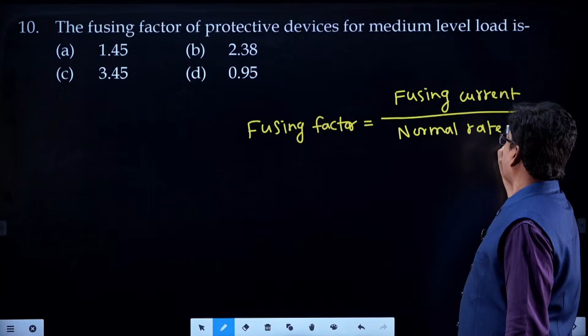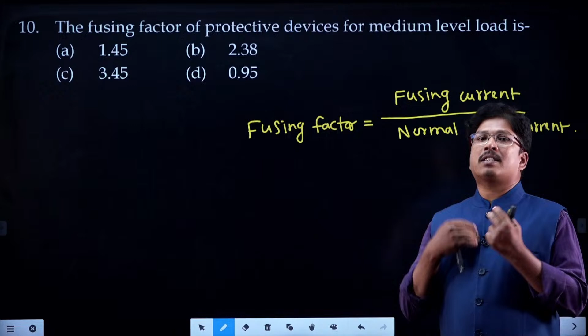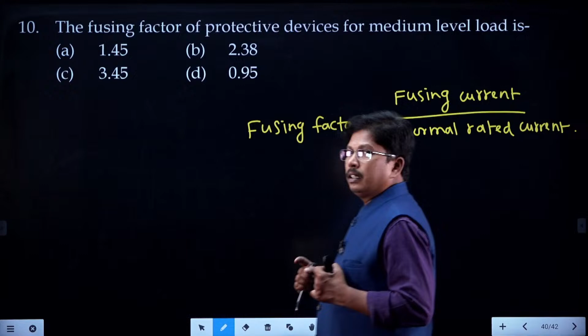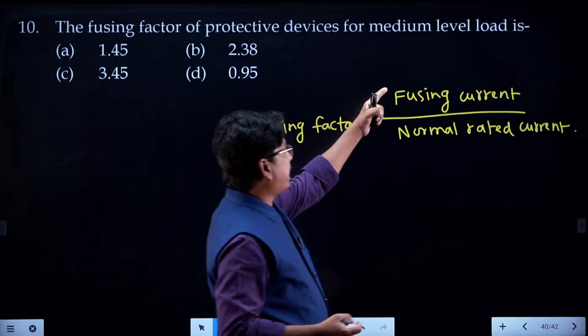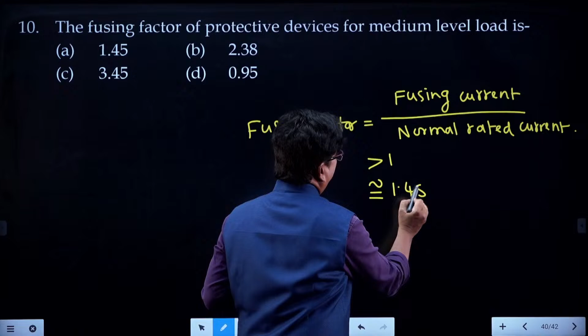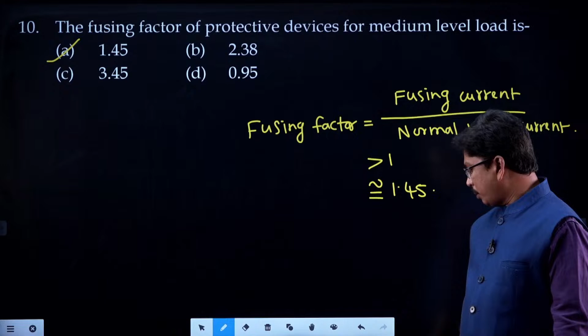Students, actually fusing current is the current at which the fuse will be melted and will open the line. Normal current means the highest amount of current that is flowing through the fuse wire without melting, right. So, at rated current, the fuse is not going to be melted. At fusing current, the fuse will be melted. Definitely, the fusing current is more than the rated current. It is always greater than 1, and its value is approximately 1.45. The fusing current is always more than the normal rated current.